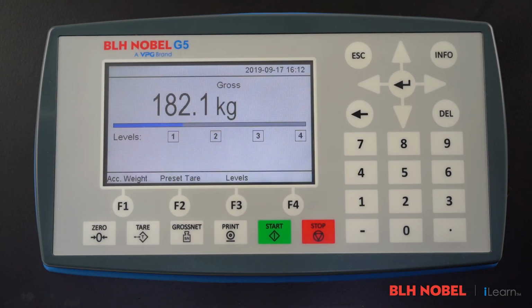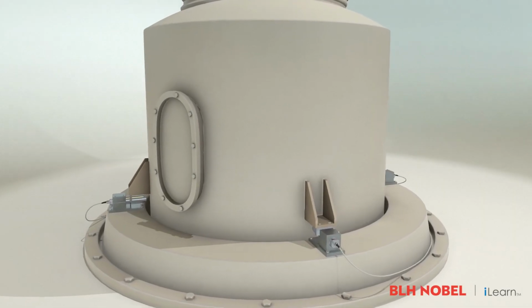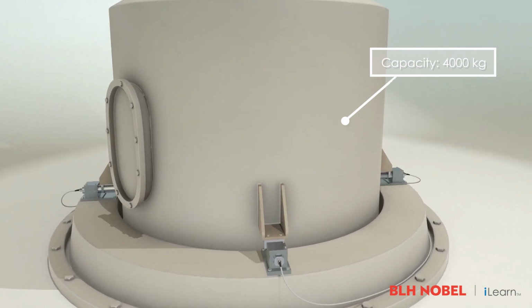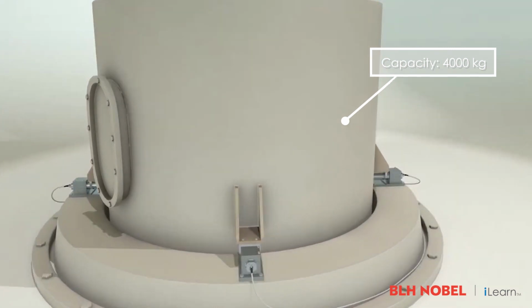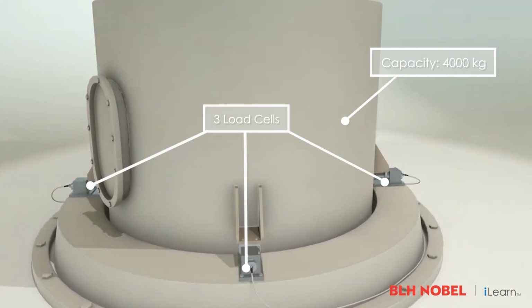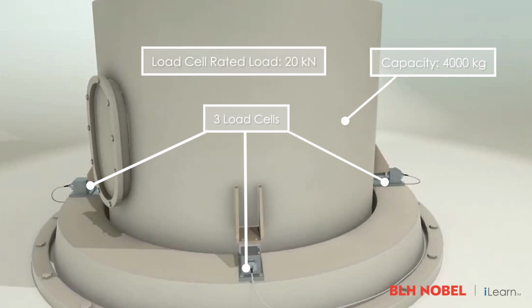Hi, my name is Nikki, and today my colleague Henrik will demonstrate how to do a parameter setup and a datasheet calibration with a G5 panel mount instrument. In this example, the tank has a capacity of 4,000 kilograms. We are using 3 load cells, and the load cell rated load is 20 kilonewtons, which you enter as 20,000 newtons in the instrument.